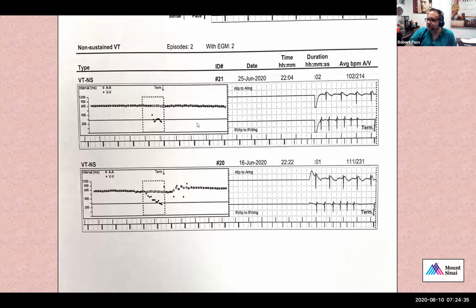Now, because of the way that defibrillators work, you can tell the device how long you want to watch the VT before the device starts to charge. And so in most patients, what I normally ask is 1 or 2 seconds. But then the device has to charge, and it normally takes a defibrillator anywhere between 8 and 15 seconds to charge. And then usually it will recheck for approximately 1 more second before it defibrillates. And so we would not have expected that the device would have shocked her for this episode.